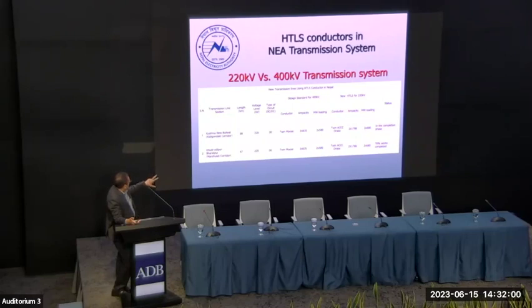The current will be the same, because over 88 kilometers, the twin moose conductor capacity is around 1350 megawatts, but using HTLS conductor at the lesser 220 kV voltage, it takes nearly 1500 megawatts. The same applies for Khudi-Bharatpur and Udipur-Bharatpur.